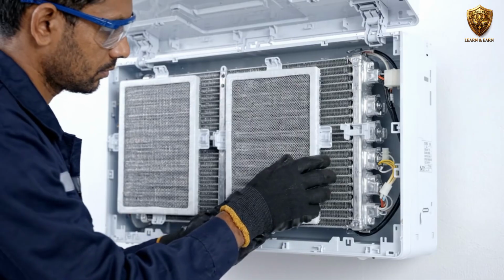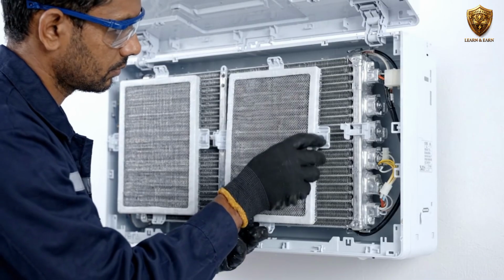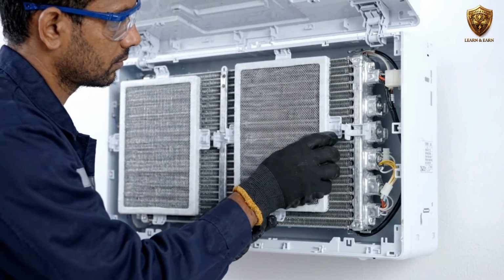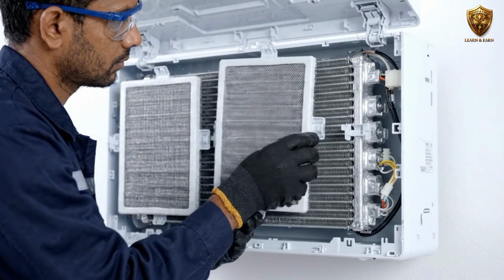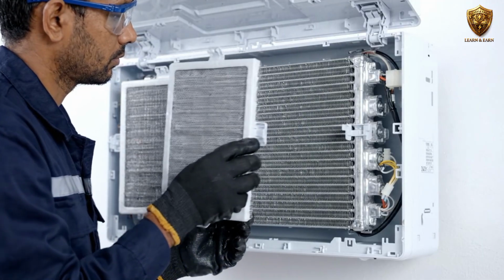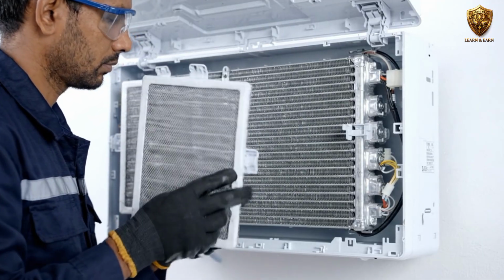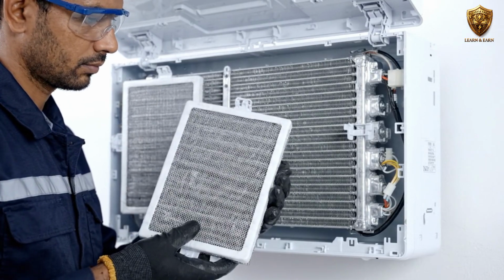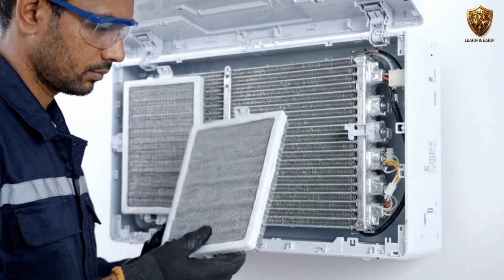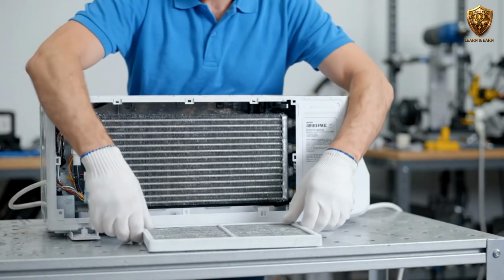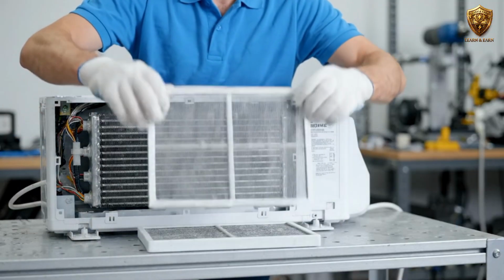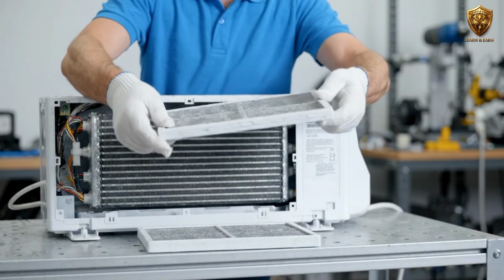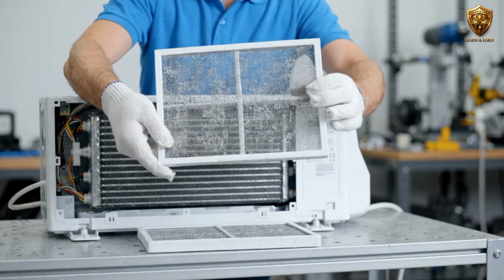Airflow is one of the first major areas to check because an air conditioner cannot deliver proper cooling if the correct amount of air is not moving across the evaporator coil. Start with the return air filter. A heavily blocked filter increases resistance and reduces airflow through the indoor unit. That can reduce cooling performance and, in some systems, contribute to coil icing. But do not stop at the filter. A clean filter does not automatically mean airflow is correct.